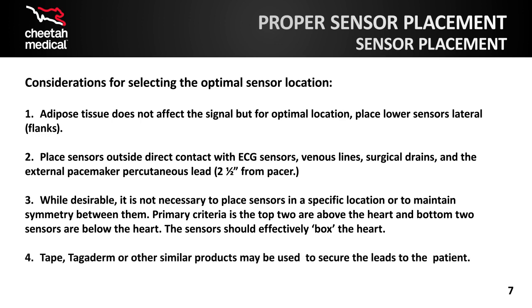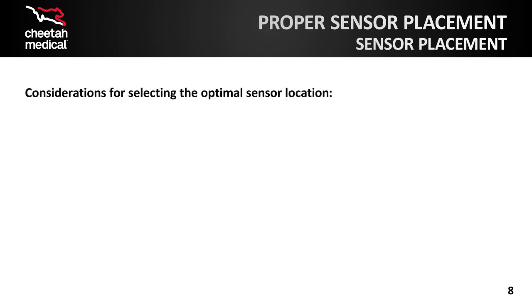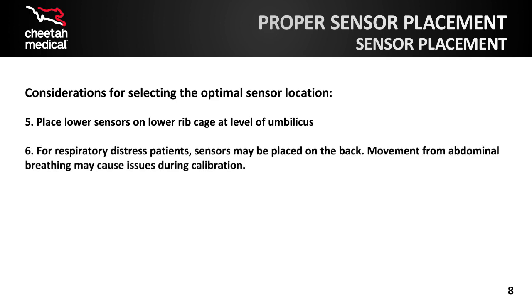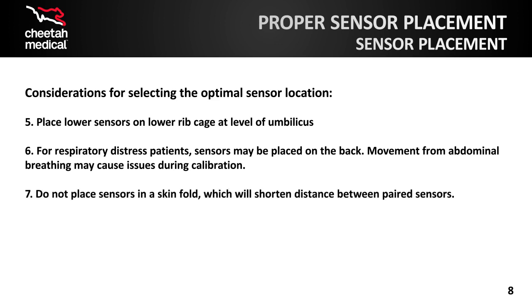4. You can also use tape to secure the leads to the patient. When monitoring during anesthesia or for long-term periods, apply Tegaderm type adhesive or other similar products to secure the lead in place. Other considerations for selecting the optimal sensor location include 5. Place lower sensors on lower ribcage at the level of the umbilicus. 6. For respiratory distress patients, sensors may be placed on the back. Movement from abdominal breathing may cause issues during calibration. 7. Do not place sensors in a skin fold, which will shorten the distance between paired sensors.